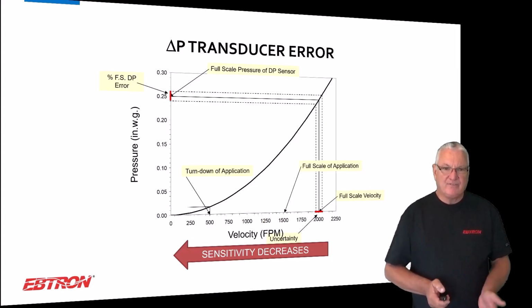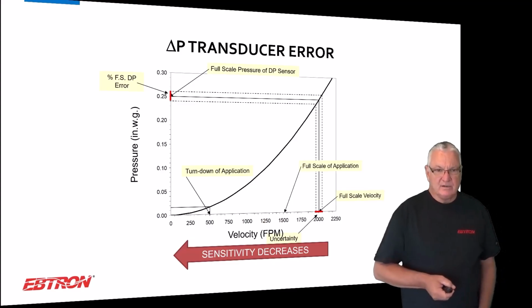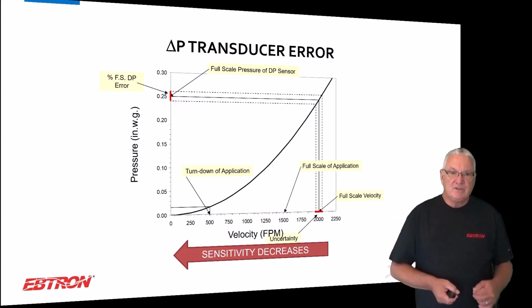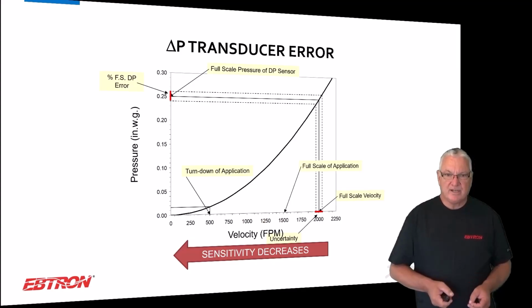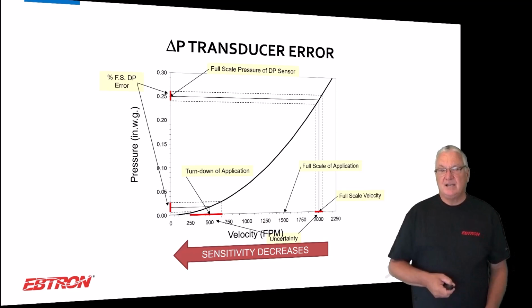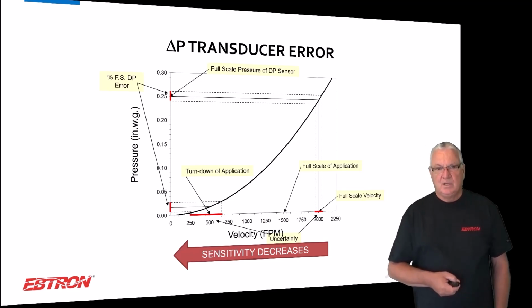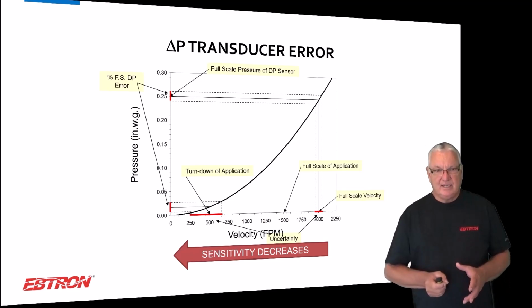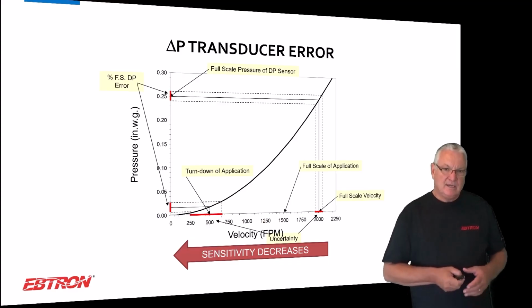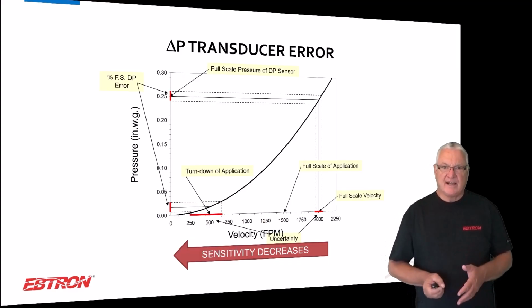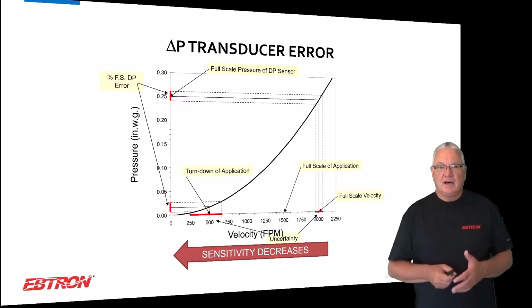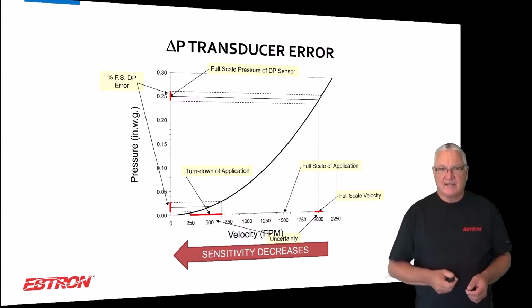All right, so now we look at 500, and it has a certain DP associated with it. Well, because you're using a % of full scale pressure transducer, the uncertainty is theoretically the same at turn down. So when you look at what that uncertainty in flow measurement is, it's huge, and it's not intuitively obvious to people. The accuracy of these DP devices varies with the square of the turn down. You turn it down 4-to-1, you're 16 times less accurate. And I don't think that's obvious to people.